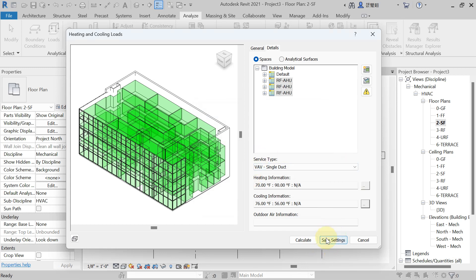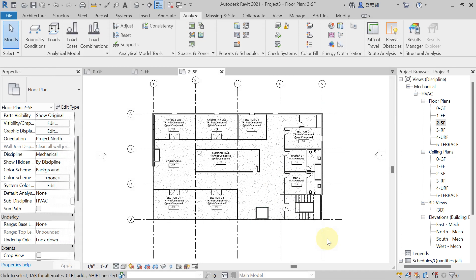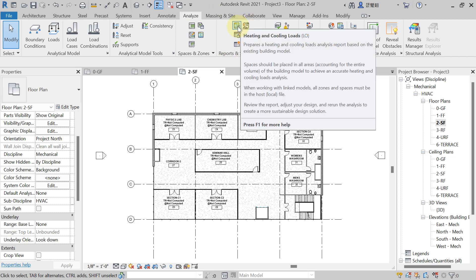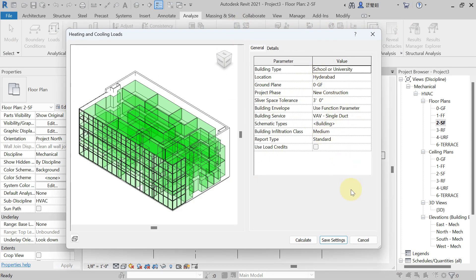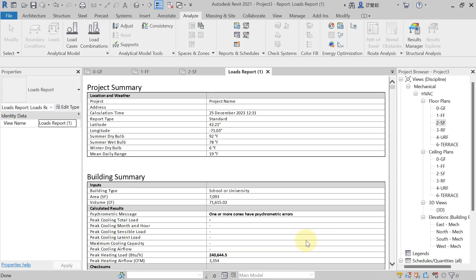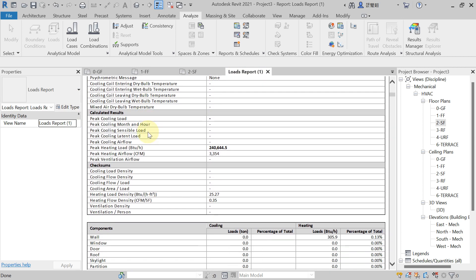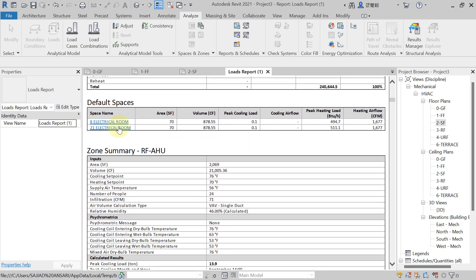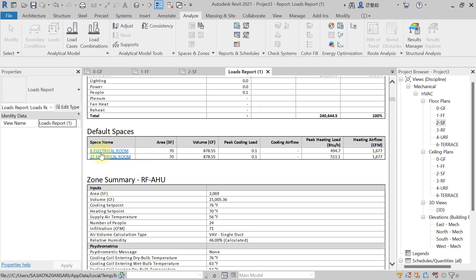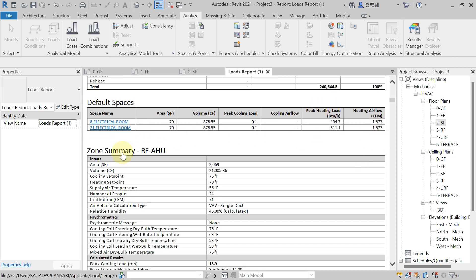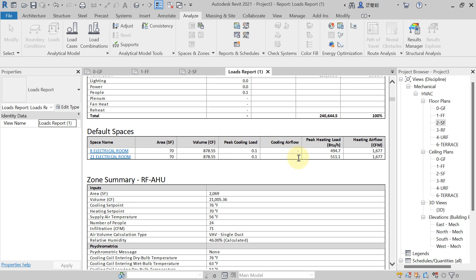Once all details are filled, click 'Save Settings.' Then reopen Heating and Cooling Loads from the Analyze tab (Report and Schedule panel) and click 'Calculate.' After calculation, the load report appears automatically — you see Project Summary, Building Summary, and Zone Summary. For default (unconditioned) spaces like the electrical room set to Vented, cooling load shows as dashed, meaning no conditioned air is supplied there.